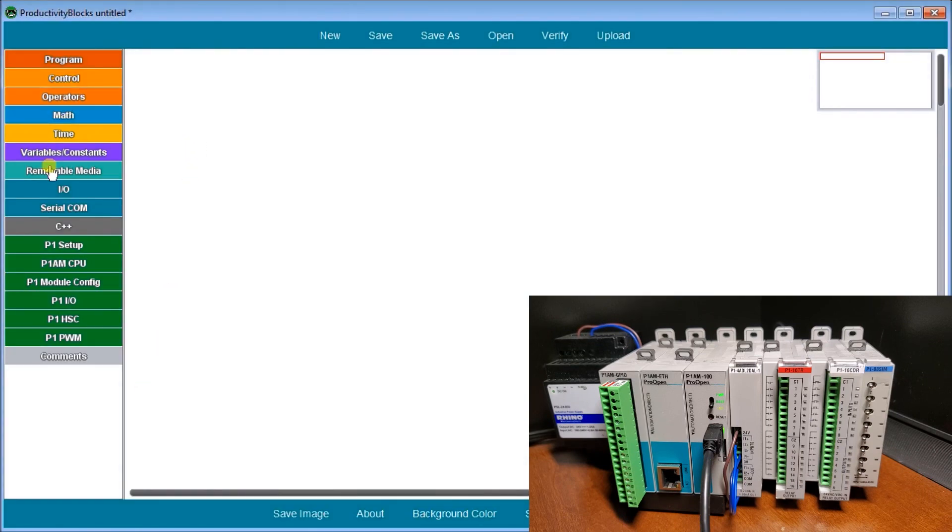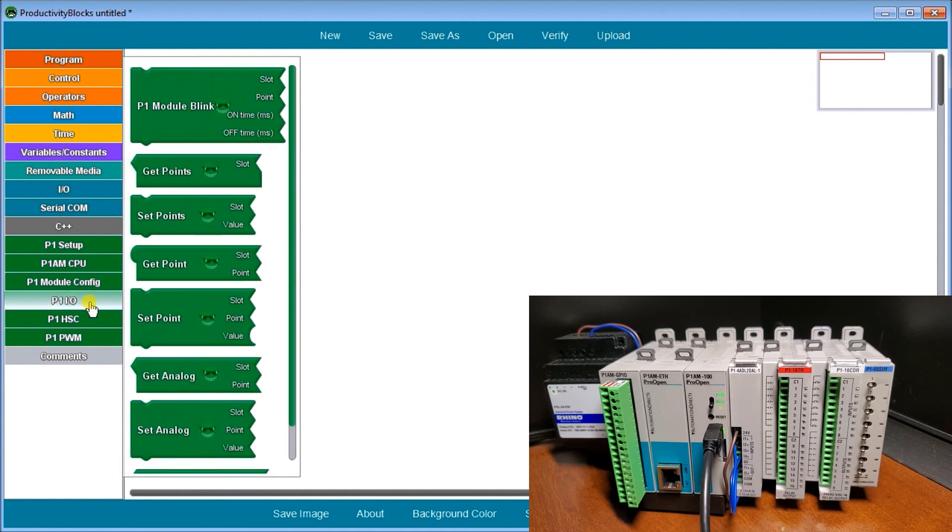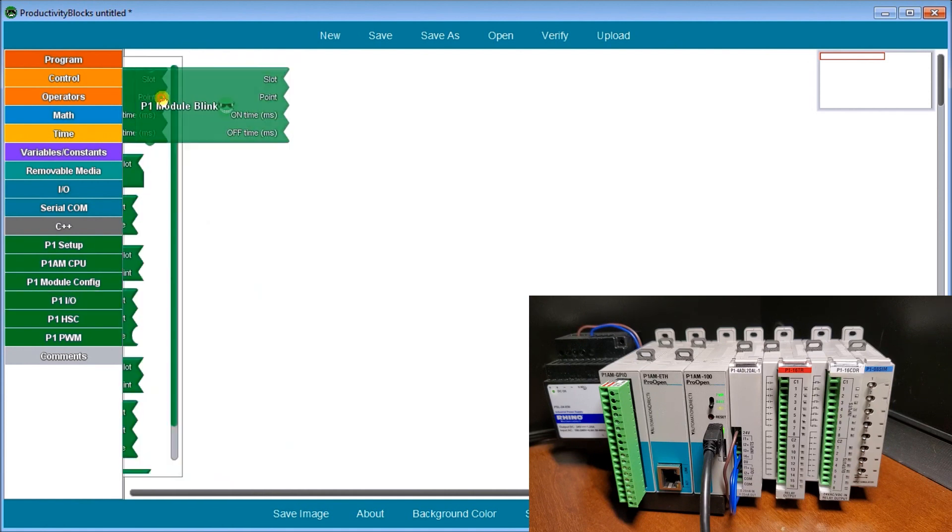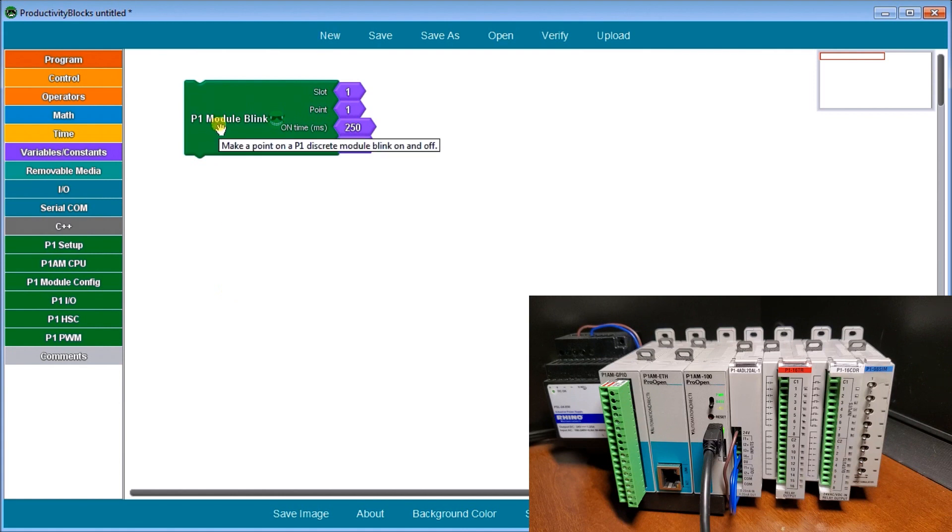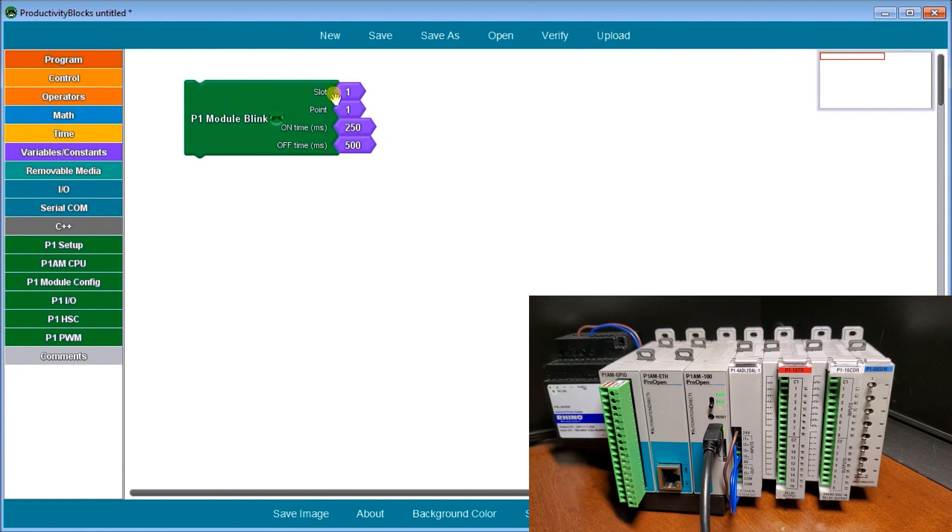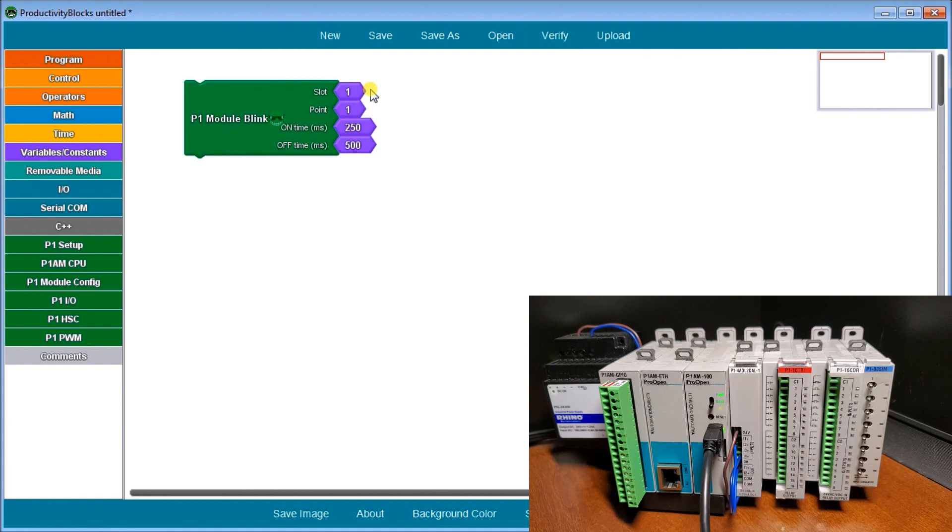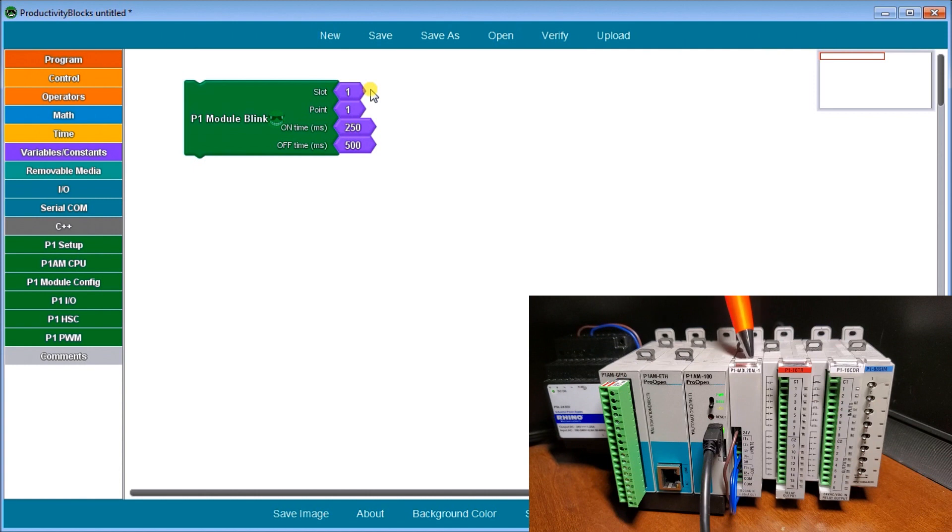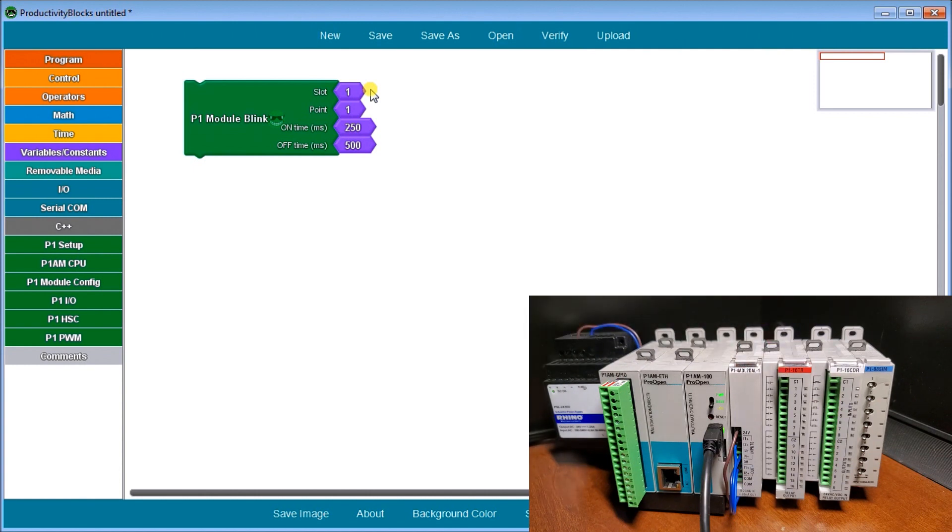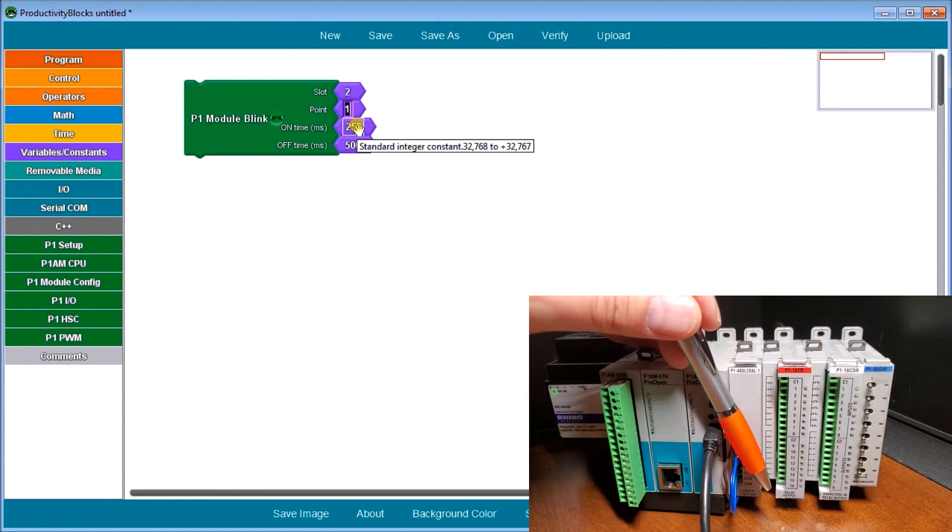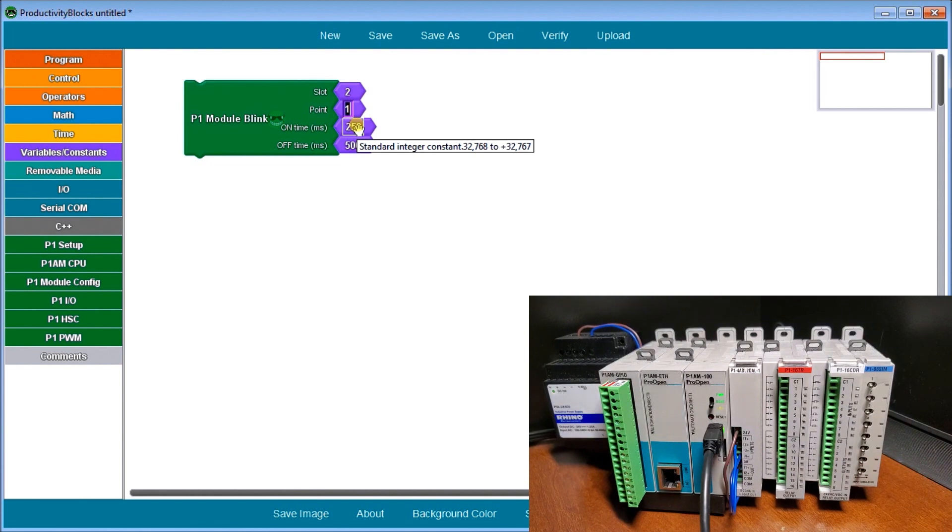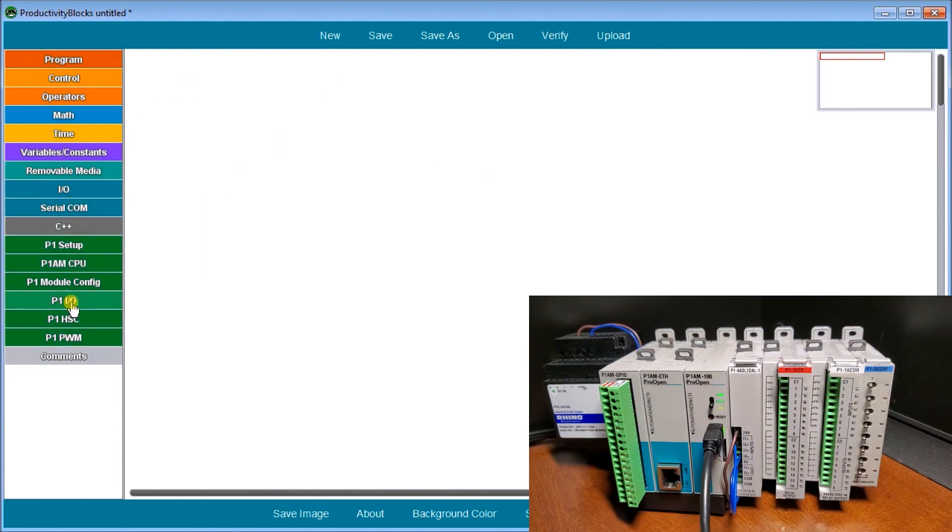Let's take a look at productivity blocks and how we program these discrete I/O points. If we go down to P1IO, these are inputs outputs. We can look at the blink instruction which will turn on for a certain time frame and then off for a certain time frame. The addressing is my slot, my point number. This would be slot two, point one all the way up to point 16.